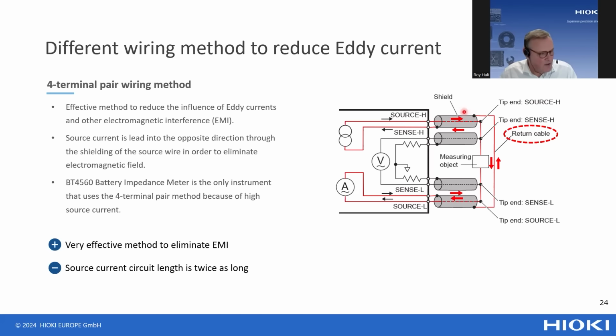But also, because of the coaxial cables, we can connect the shielding of the coaxial cables for the sense wires to Earth, which gives very good protection against electromagnetic interference from all kinds of other signals in the production line. So it is very effective for eliminating EMI.